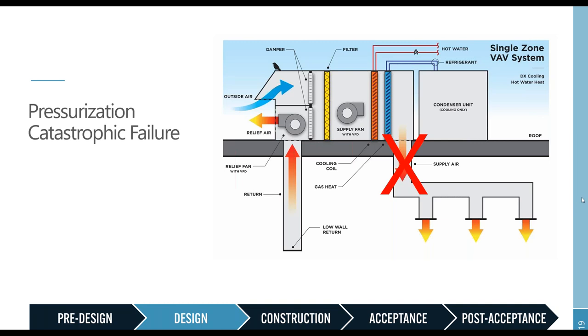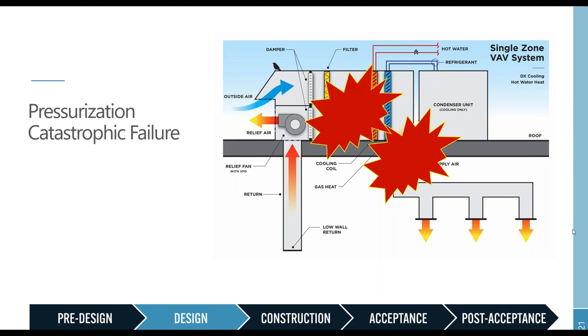Pressurization. Now, surprisingly, one of the most common issues I find is the designer forgets to install a physical safety on the air handling unit to prevent the fan from over or under pressurizing a ductwork system. Typically, this occurs when the startup technician or even the building engineer manually controls the fan, but forgets to open or close the airflow dampers, giving the air nowhere to go. Excuse my poor graphics. Pressure builds and builds until either the ductwork seams burst or the fan fails. The building engineer could be controlling the system from their office in the basement, and they would have no idea until they go up and investigate.